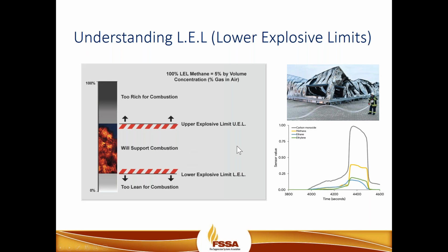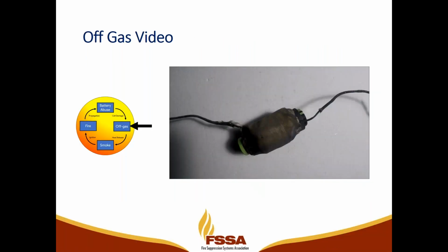And that's really what happened at the APS fire: the off-gas continued and the abuse factors continued throughout thermal runaway, and filled the space with methane over a 3-hour period while firefighters were fighting from the exterior. And as they looked to breach the building, they introduced oxygen into the space, creating an explosive environment. So I put together a couple different videos for you to review.